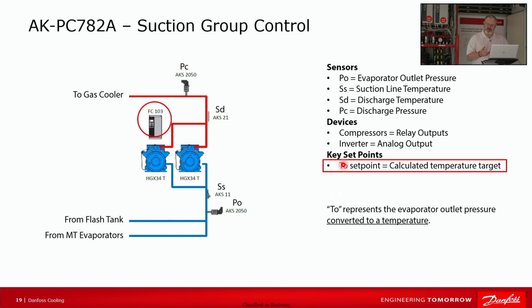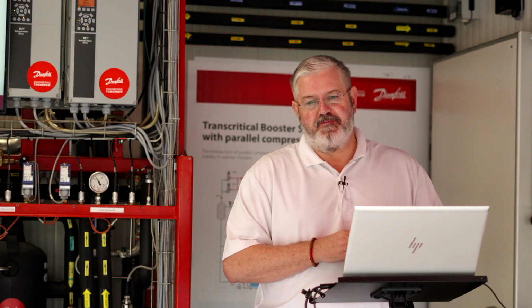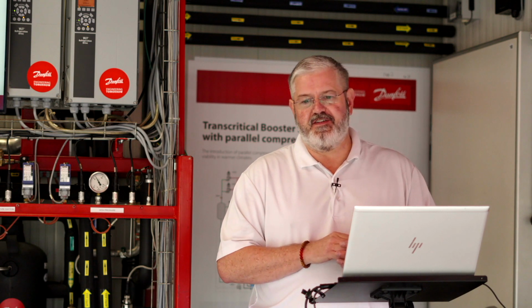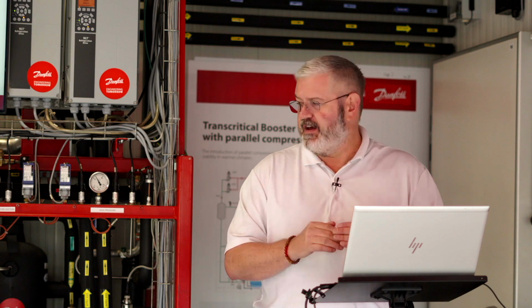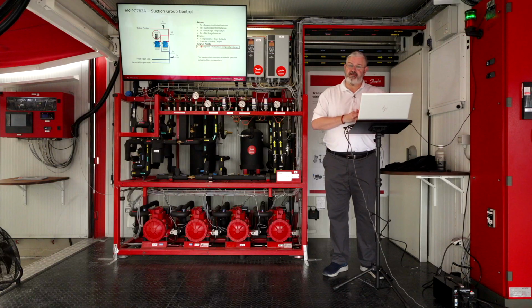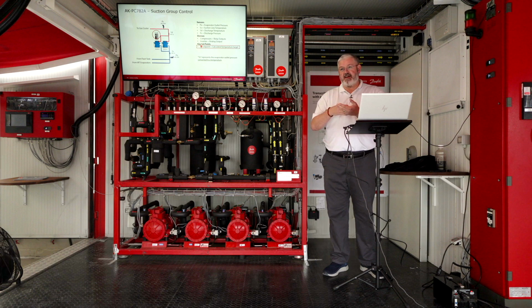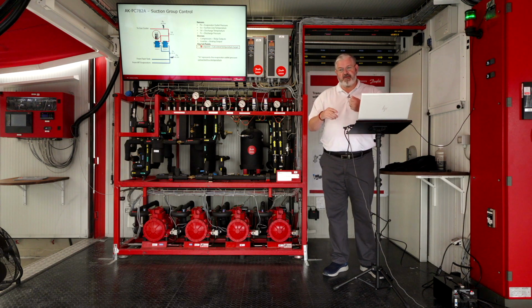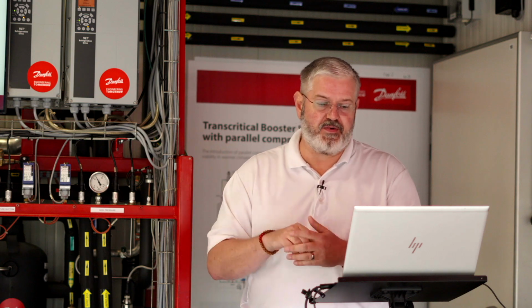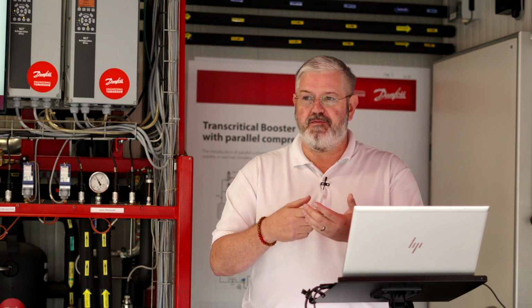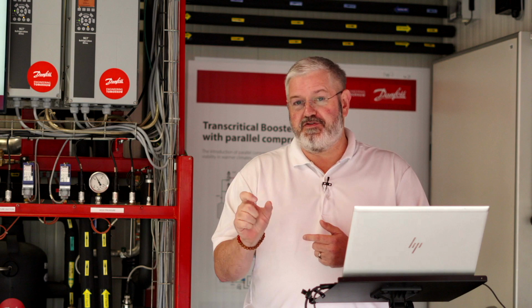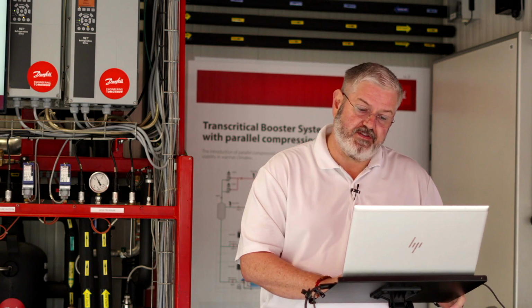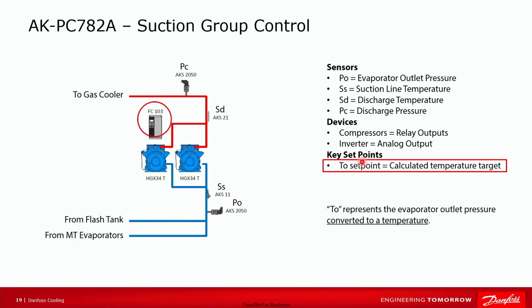The reason that we do that is it's very common, maybe even on some of our legacy devices, that you put your set point in for your suction groups as a pressure. And so that causes you to need a PT chart everywhere you go, either in an app or in your pocket, to pull out and determine plus 20 means 44 pounds, 44 pounds is my set point. We simply do that lookup in the background for you. You just put in the temperature you want, and then we reference this transducer and convert that to a temperature.